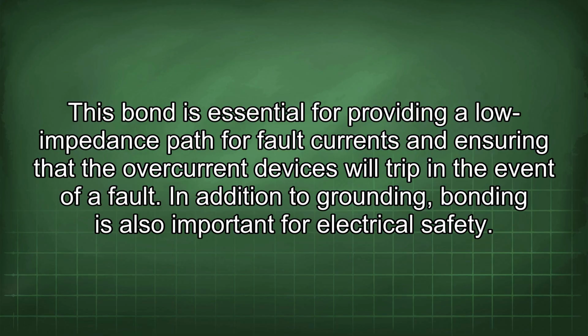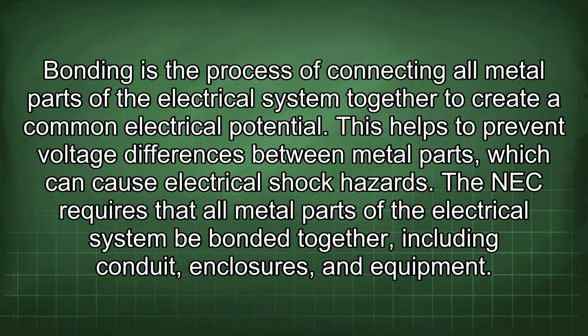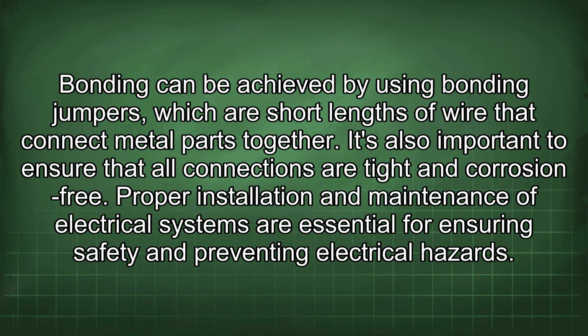In addition to grounding, bonding is also important for electrical safety. Bonding is the process of connecting all metal parts of the electrical system together to create a common electrical potential. This helps to prevent voltage differences between metal parts, which can cause electrical shock hazards. The NEC requires that all metal parts of the electrical system be bonded together, including conduit, enclosures, and equipment. Bonding can be achieved by using bonding jumpers, which are short lengths of wire that connect metal parts together. It's also important to ensure that all connections are tight and corrosion-free.